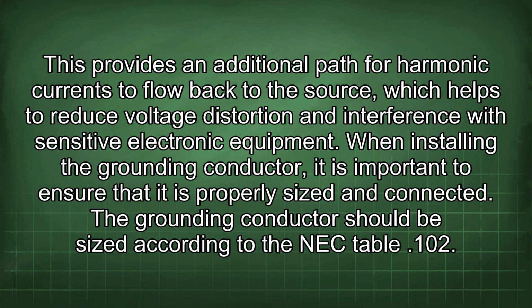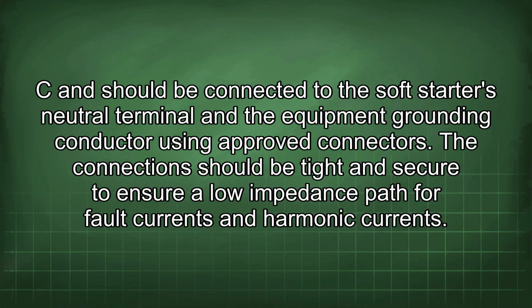When installing the grounding conductor, it is important to ensure that it is properly sized and connected. The grounding conductor should be sized according to the NEC table 102.C and should be connected to the soft starter's neutral terminal and the equipment grounding conductor using approved connectors. The connection should be tight and secure to ensure a low impedance path for fault currents and harmonic currents.